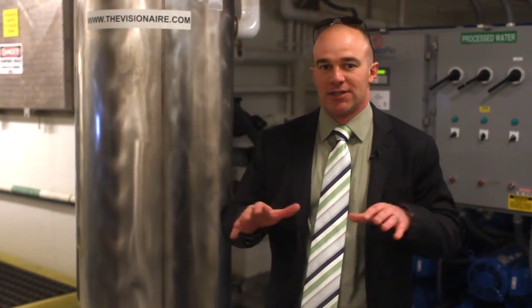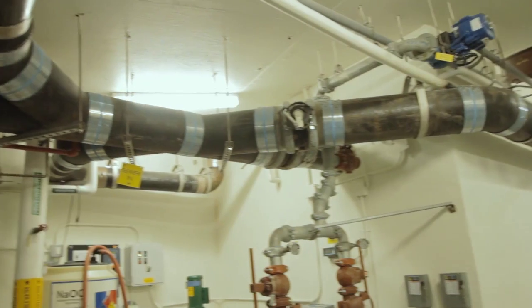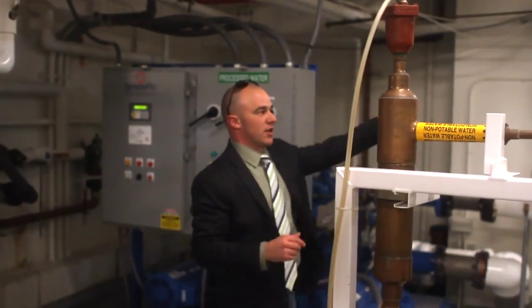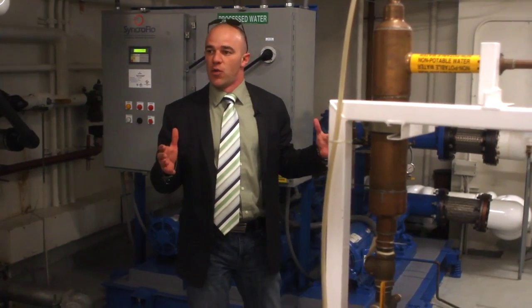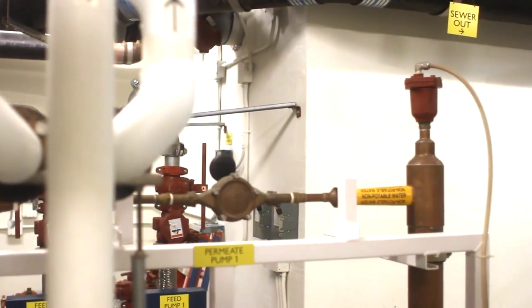We are now in the basement of the Visionaire, this 450,000 square foot building. In less than 2,000 square feet in this room, we treat all of the wastewater for the building. It all flows above us in this big black pipe and enters into the feed tank, which is an equalization tank that holds raw wastewater until we're ready to process it and as we need it for the reuse purpose.